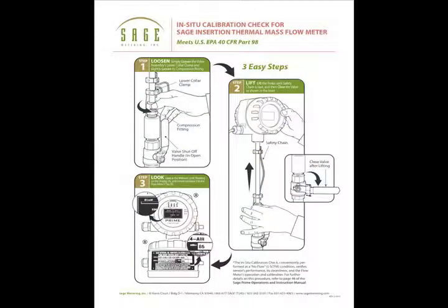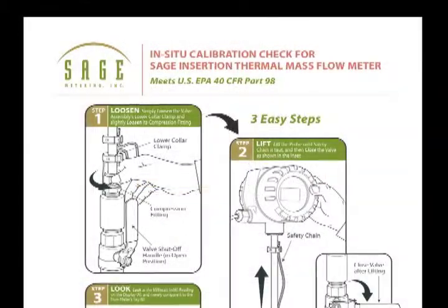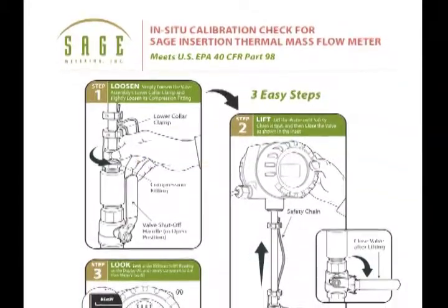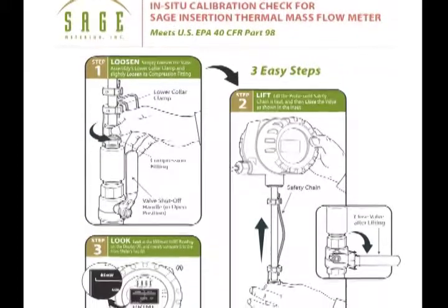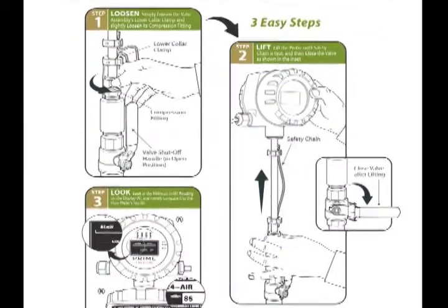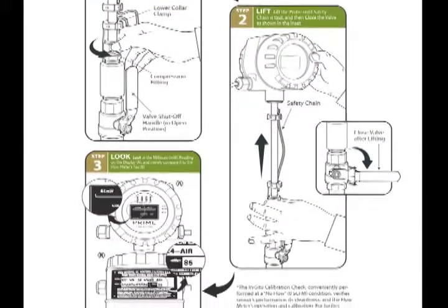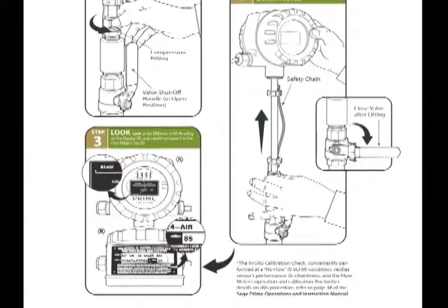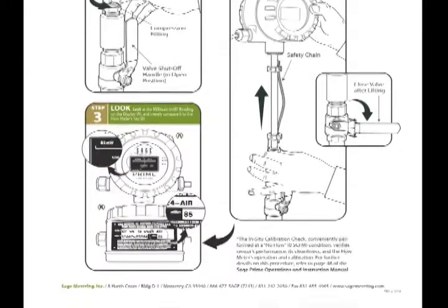Perhaps our most notable contribution to the industry was the introduction over five years ago of the in-situ calibration check, which eliminates the cost and inconvenience of periodic factory recalibrations. This three-minute check at a no-flow condition is reliable, regardless of the test gas temperature, and assures that your sensor is clean and that the flow meter hasn't drifted, shifted, or changed since its initial NIST traceable factory calibration.